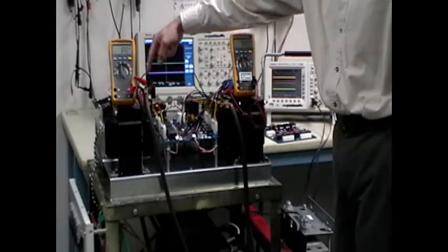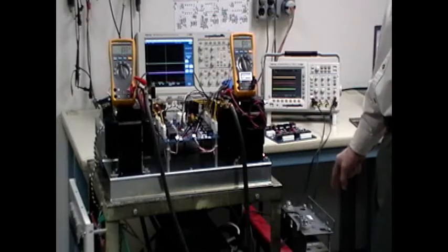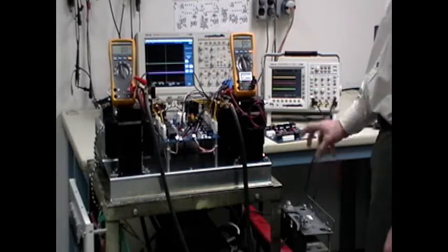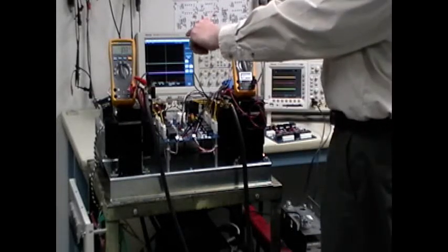We have our two independent three-phase full-wave rectifiers, each with their own filter inductor that feeds our four-kilowatt load. We're going to be putting about 200 amps into the load, and we're going to be trying to match 100 amps out of each bridge.